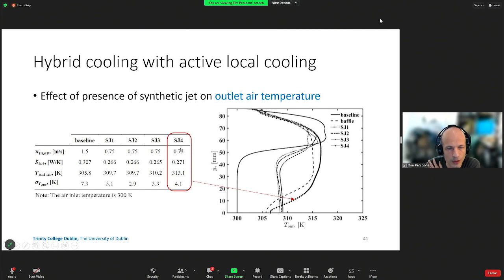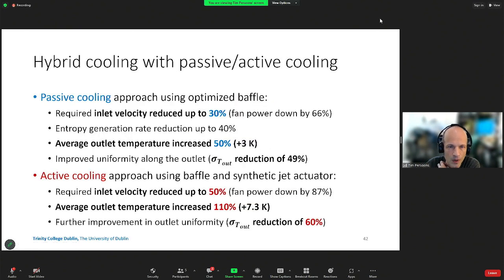The flow is reduced by approximately 50%, and our uniformity is okay. I mean, it's never perfect, right? You still have some non-uniformity, but this was apparently the best combination in our view. So as a result, if you look at the whole approach of both passive cooling, just using baffles, or active cooling, a combination of baffles and synthetic jet actuators, we're able to reduce the inlet velocity quite a bit while still making sure that the components are cooled sufficiently.